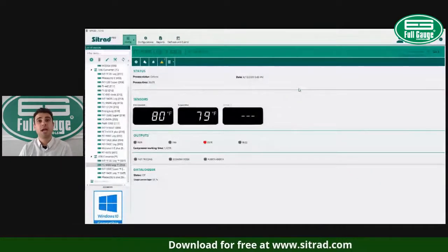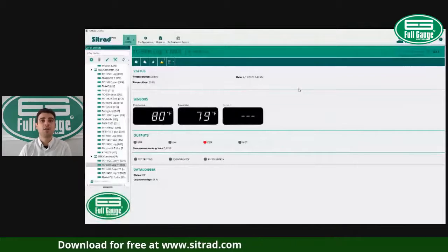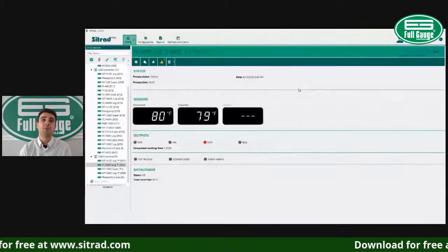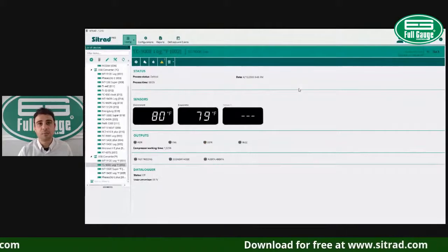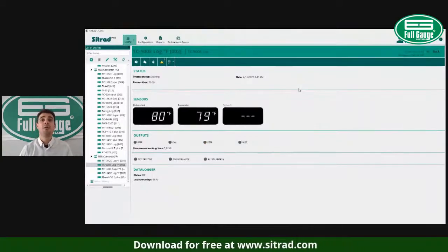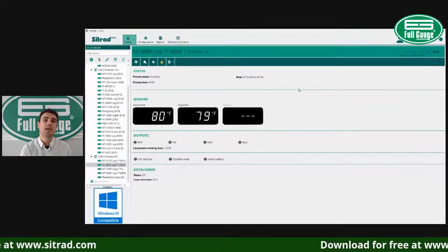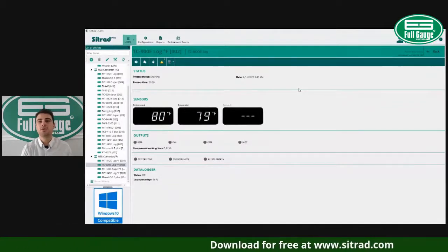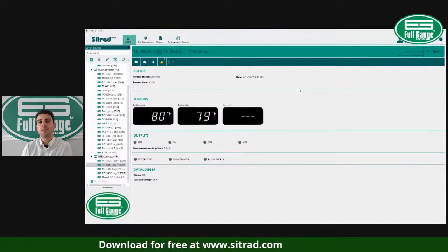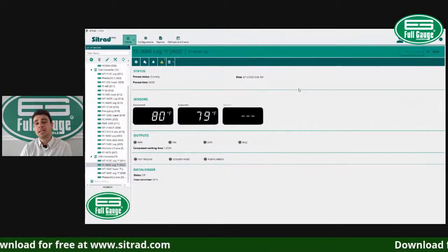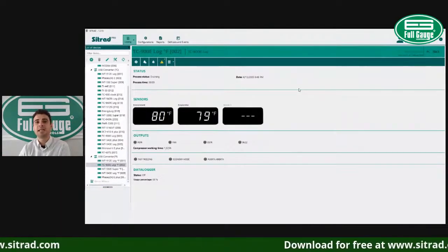So you might have to check why that happened, or if that is constantly happening, maybe your defrost termination temperature is too high, or maybe there are other things to look at. But that's why we had the alarm, because this controller wants to terminate the defrost always based on the coil temperature. And in this case, unfortunately, terminated by time.